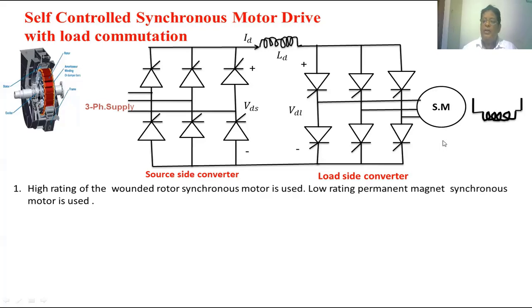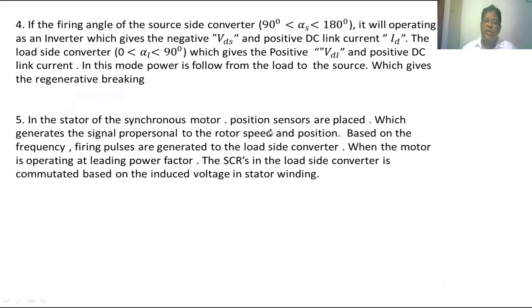For high rating synchronous motor drives, we use wound rotor synchronous motors. For low rating, the synchronous motor will be a permanent magnet synchronous motor. In the stator of the synchronous motor, position sensors are placed which generate a signal proportional to the rotor speed and position. Based on the frequency, firing pulses are generated to the load side converter. When the motor is operating at a leading power factor, the SCRs in the load side converter are commutated based upon the induced voltage in the stator winding.